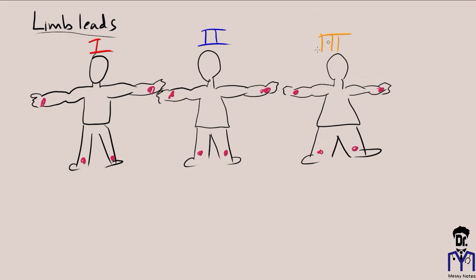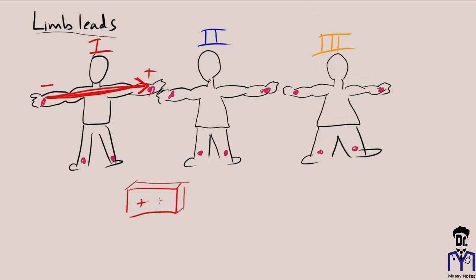To create Lead I, we make the left arm positive and the right arm negative. We're comparing the electrical potential differences between the positive and negative ends, and this creates a lead. The right ankle will always be your ground. The angle of orientation for Lead I will be 0 degrees.